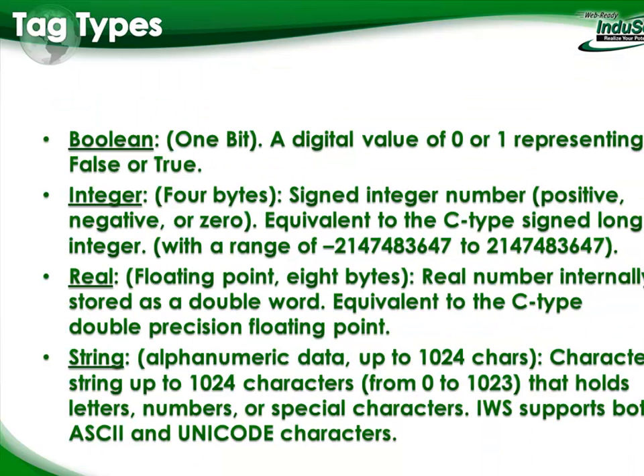We have four main tag types: Boolean, Integer, Real, and String. Booleans are just a bit — a digital value of 0 or 1 representing false or true. In InduSoft Web Studio, a non-zero value is also considered true. So not only 1, but 10, 100, or 235 are also considered true, as well as a negative number — as long as it's non-zero. If you write a negative number into a Boolean, it will come up as true.